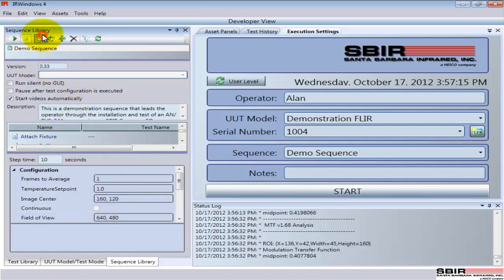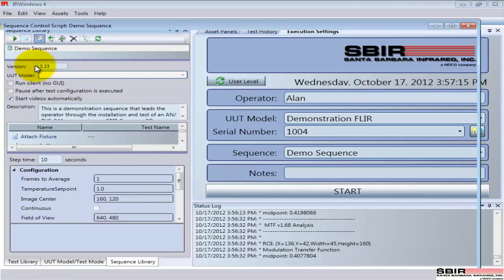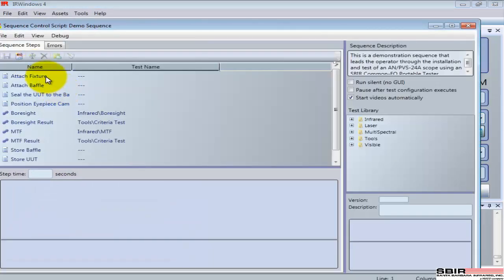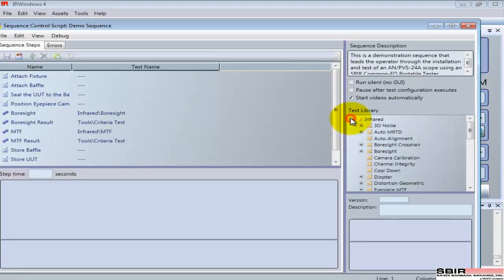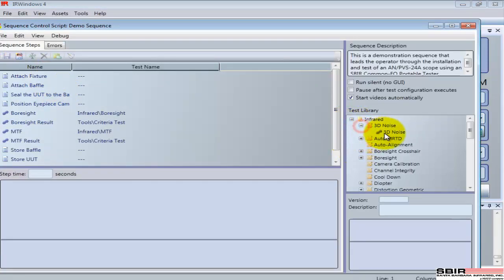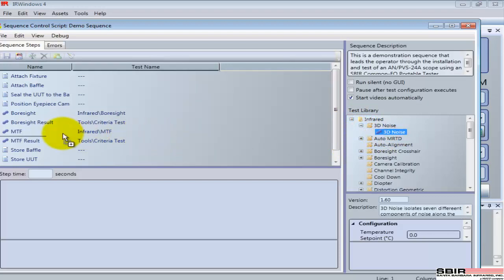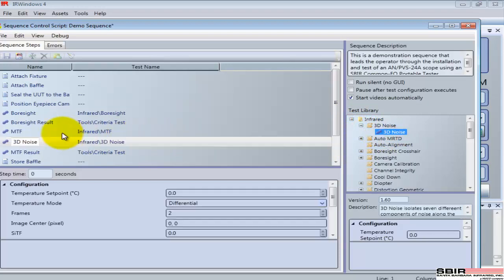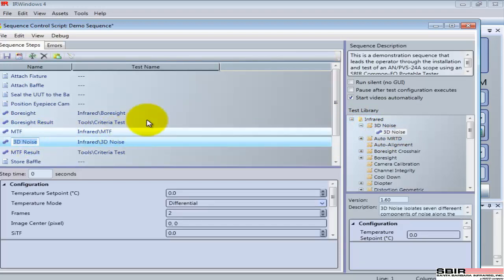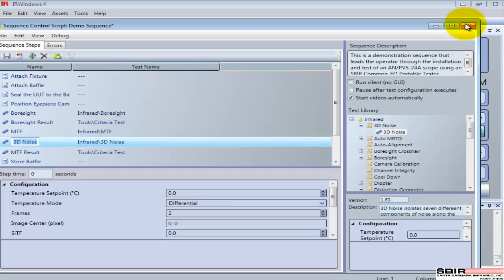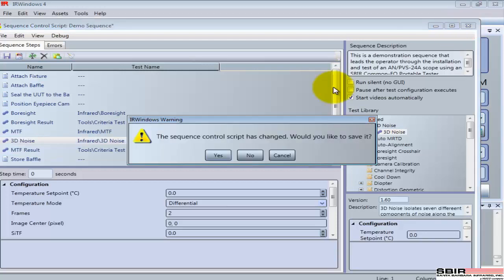I can edit this configuration and come in and add additional steps. Here are the steps. I've got the test library, so I can grab some other results. Let's say I want to grab a 3D noise test, grab it and pass it over in. I have a way of configuring that, changing that. I can make alterations. This is all in the developer's view because it's the developer who's setting up these test configurations and scripts for the operator to run, or for themselves to run.